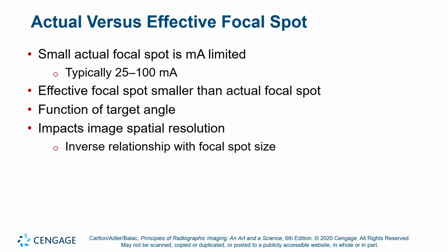The actual focal spot is mA limited. So if you want a small focal spot that gives you better detail, better spatial resolution, you're limited as to your total tube current. You can't concentrate that many electron bombardments in that small of an area. Your typical small focal spot is about 0.6 of a millimeter by 0.6 of a millimeter.